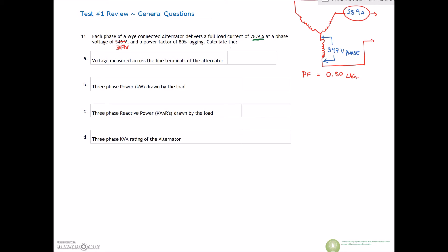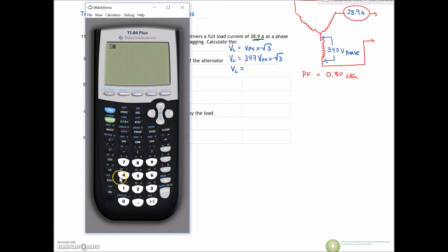Let's just double check. Our line voltage is equal to our phase voltage times √3. So our line voltage equals 347 times √3. That's why I noted the lower value of 346, because this is just going to be a touch higher than 600 volts. Let's take a look — 347 volts... let me put that into the calculator properly.